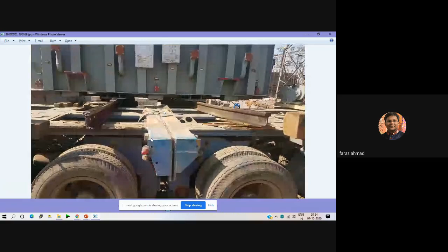This is a reactor, a component that helps stabilize the reactive power of the grid. We installed a bus shunt reactor recently, rated for 400 kV. However, due to the long length and the Ferranti effect, voltage levels often reach 420 kV, and that extra 20 kV stresses every equipment of the power plant and switchyard, which is very dangerous. To compensate for this extra voltage, we installed a shunt reactor.